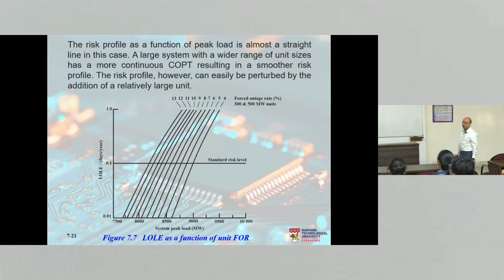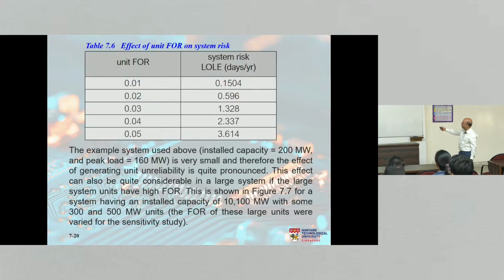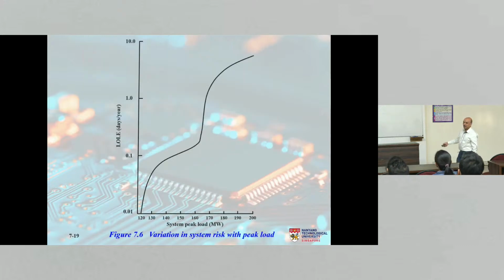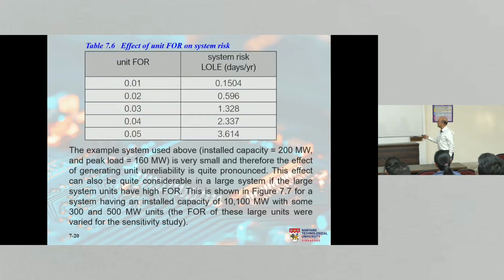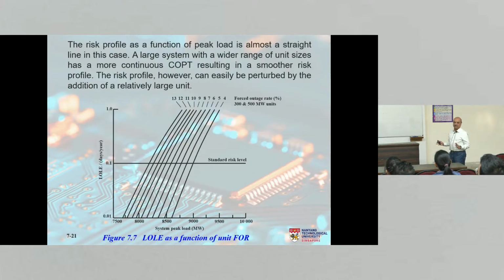So you see what we did? We changed the forced outage rate of these 300 and 500 megawatt units from 4% to 13%. And you can see the impact on the risk, yeah? And as you see, the profile is smooth. If you go back to this one, the profile is not smooth, yeah? So when you have a small system, the perturbations in the risk are significant. But when you have a much larger system, the perturbations will usually be smoother. But if you add a very large generator, if you add a 1,000 megawatt generator, then this risk profile will not be so smooth. So all these factors need to be taken into account, but at least we have the tools, we have the resources to be able to come to a quantitative figure which we can use to justify any reinforcements.